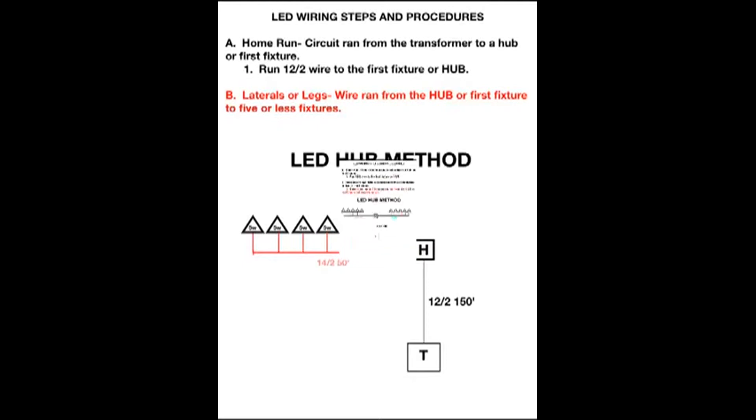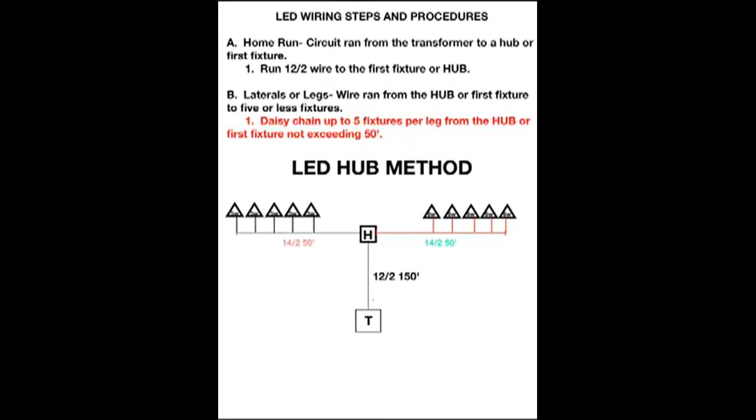You can daisy chain up to five fixtures per leg from the hub or the first fixture, but make sure you don't exceed 50 feet. This is the 5/50 rule.